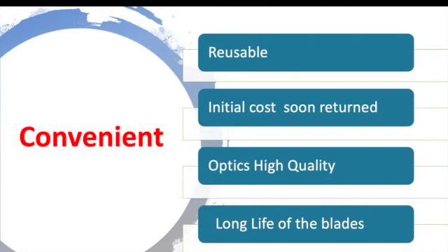With the 19 French optics, you just have an inflow. On the other side, you have the shaver, where you must prepare an additional pump, the Endomat C, connected to another engine. So you have these two units, and you have to connect the handle with these two units. Let's say that after two or three times that they do the setup, the nurses actually prefer to use the shaver than the resectoscope, because in the end it is much easier.